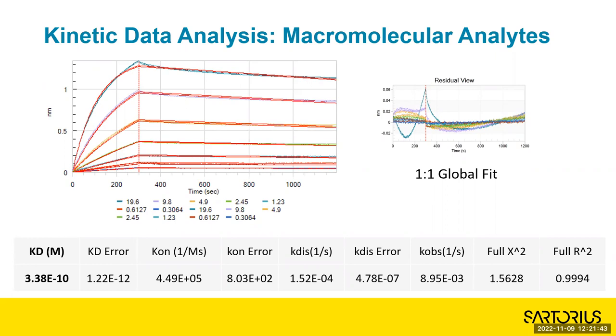You also get fitting criteria like chi-squared and R-squared. R-squared, closer to one the better. Chi-squared is a measurement of the amount of error between the fit - the lower the chi-squared, the better the fit. You also have the residual distance between the fit line and the data at every second along the curve. Typically you want less than 10% residual. If one concentration is way off but the other six or seven show good fit, maybe you should eliminate that top concentration because it's too high.